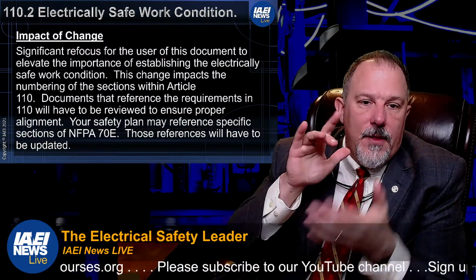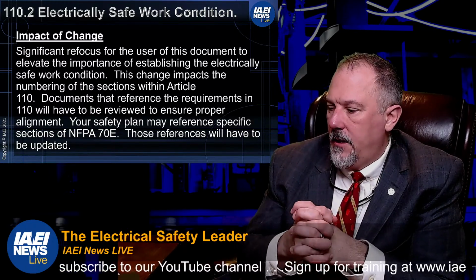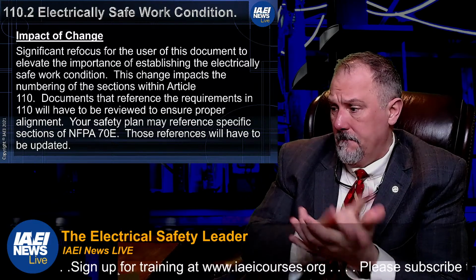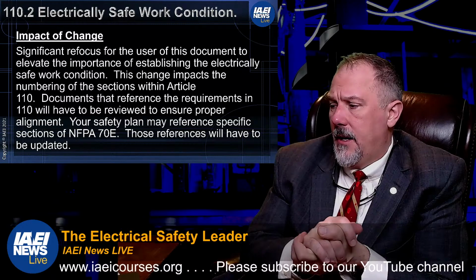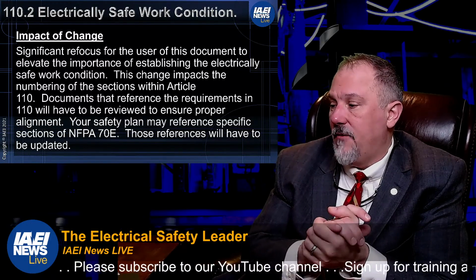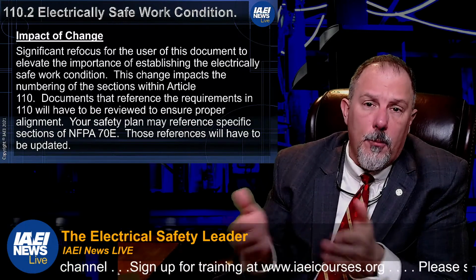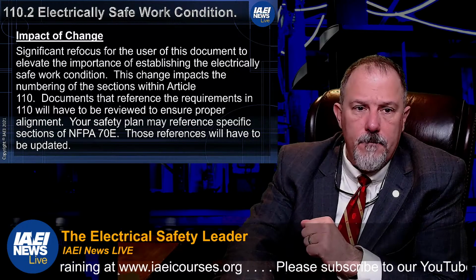All right, so this is a refocus, and I would argue that I don't see anything in 110.2 outside of creating a policy, where the owner would have to create a policy, because it does say an employer shall establish, document, and implement an electrically safe work condition policy. And I think you probably have already had that in your plan. Hopefully that is your priority 1, is to establish an electrically safe work condition. So maybe nothing changed at all.